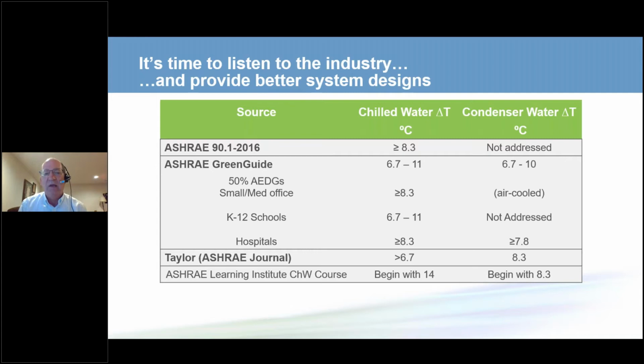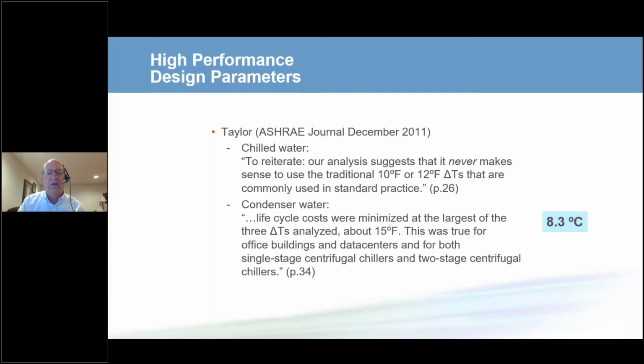Steve Taylor, who's one of the foremost chilled water plant design experts in the world, wrote a series of five ASHRAE Journal articles. They're available to ASHRAE members for free on the ASHRAE technology portal. And in his third article, he talked about design parameters, and he also said, reduce the flow rates, increase the temperature differences. And ASHRAE, either a year or two years ago, put together a new chilled water design course. In that course, it says begin with a 14 degrees C delta T, which is a larger delta T than normal. So all of these industry recommendations are saying, let's have a higher temperature difference and a lower flow rate.